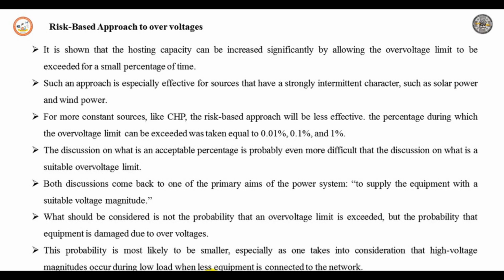Although there are no detailed studies to confirm this, before a risk-based approach can be implemented, the equipment manufacturers, standardization organizations and regulators have to get involved in this discussion. The risk-based approach is not simple and may require a significant effort before it can be widely used. However, it has the potential to increase the amount of distributed generation that can be connected without any additional investment in the distribution network.